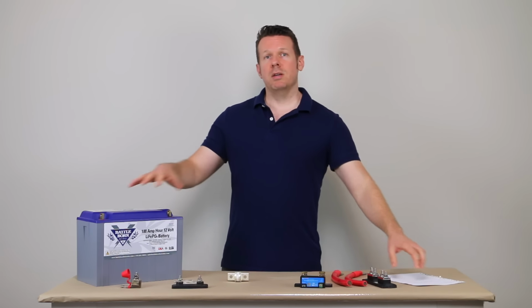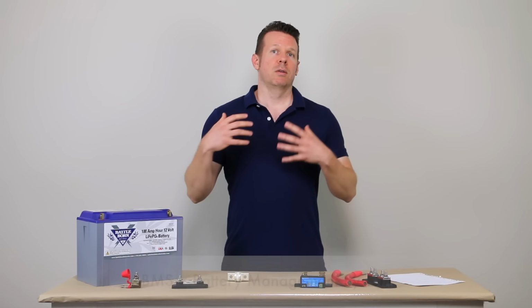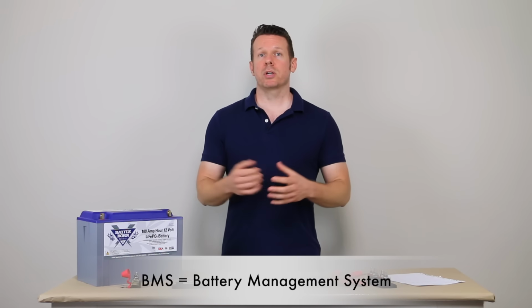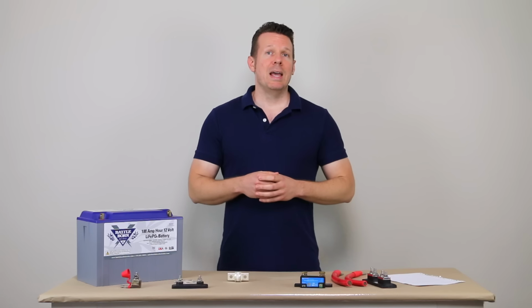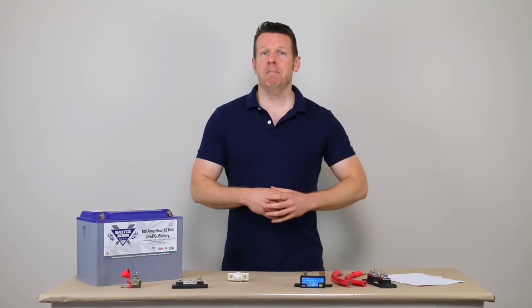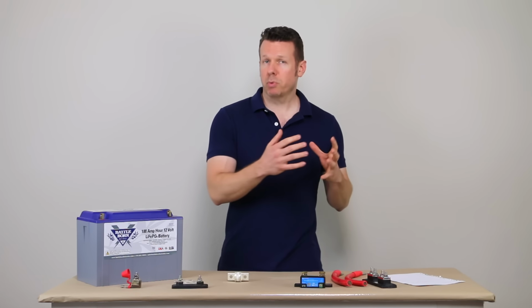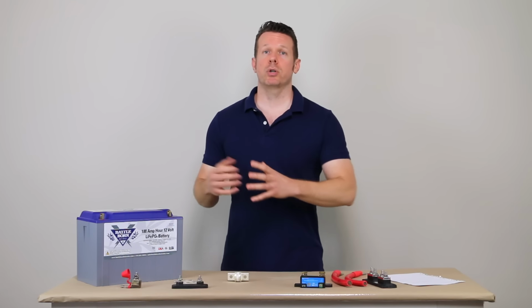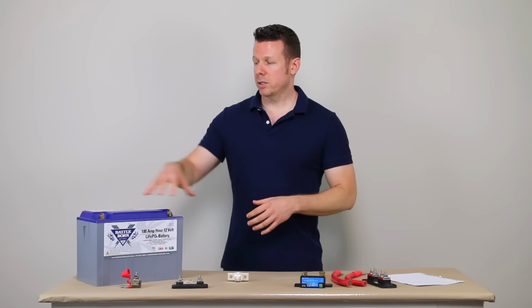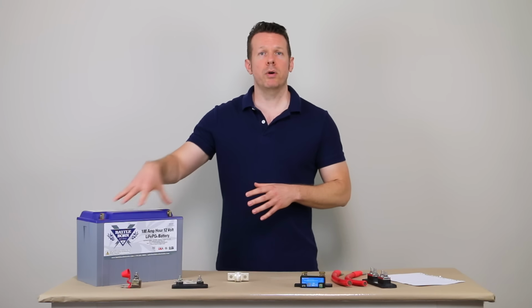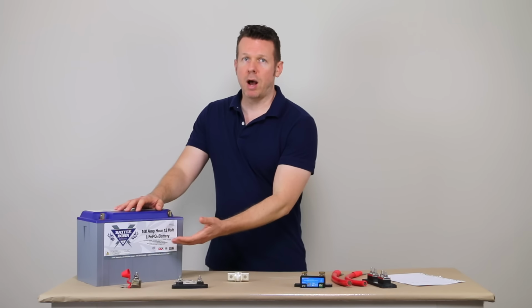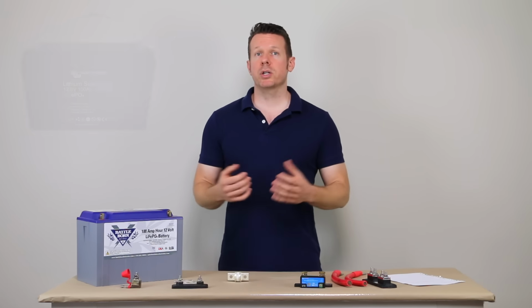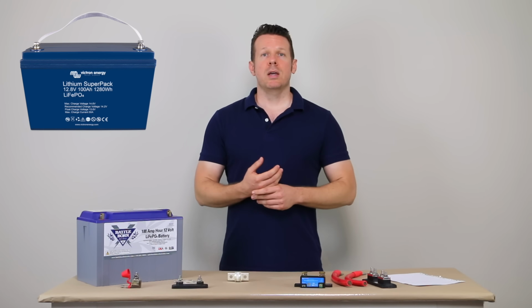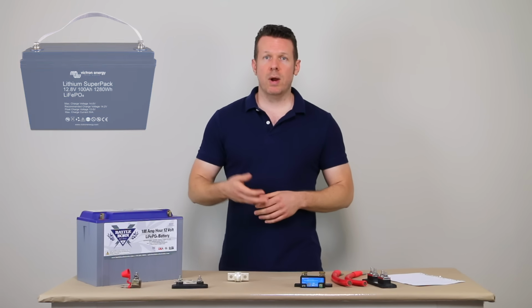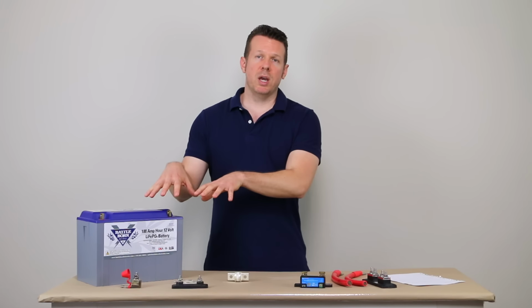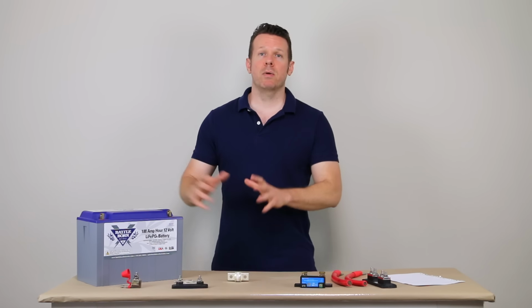Number 1 is the battery BMS doesn't have enough capacity for that particular system. I spoke to a guy and his system would work most of the time, but it would mysteriously shut down sometimes when it was charging and sometimes when it was discharging. What it was is he had 2 100 amp hour batteries, but they could only put out 50 amps each. They were the Victron Super Pack regular batteries, and they will only take 50 amps in or out of the battery. So 2 of them together was 100 amps in or out of that battery bank.